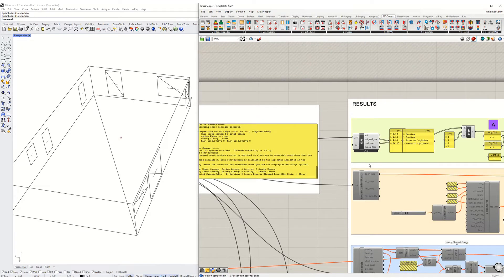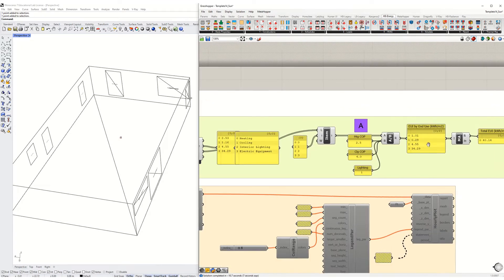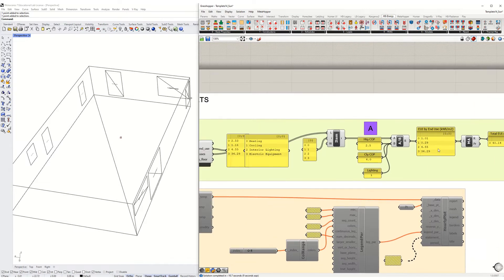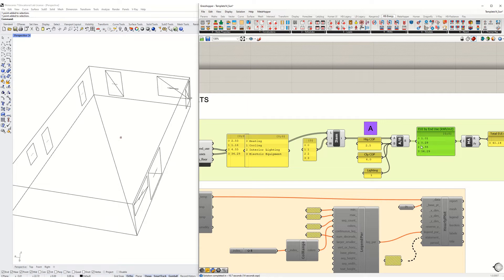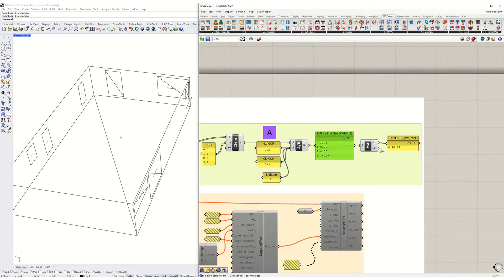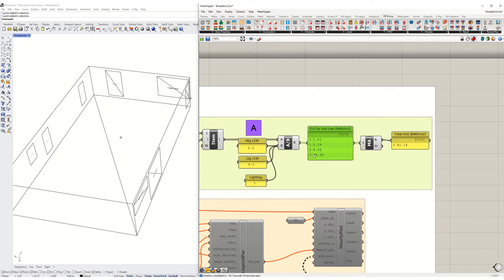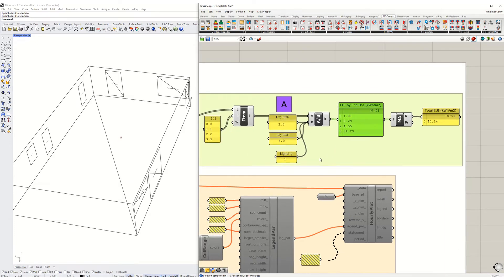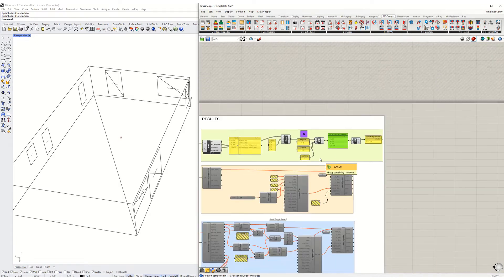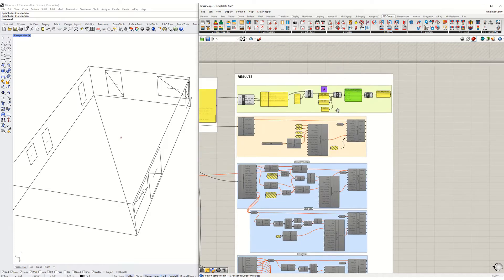So I come over here and lo and behold, my third number, which was something like 14 before, is now 4.55. So I've pretty dramatically reduced it along with my total EUI here. And notice now I've got my heating way down, my cooling's way down, my lighting's way down. The only thing left is equipment. And we'll talk about what to do about that a little bit later in class.